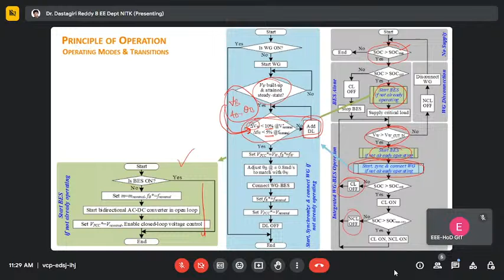First you need to see voltage is building up, and then adjust the dump load of wind so as to become reasonably close to nominal values. So VB, FB, and theta B we are adjusting to match the wind. But if the wind is too far off, like it is 550 and your nominal is 415, which is not allowed, so we use dump load to bring those voltages and frequencies close to certain values, and then we start adjusting VB, FB, and theta B.